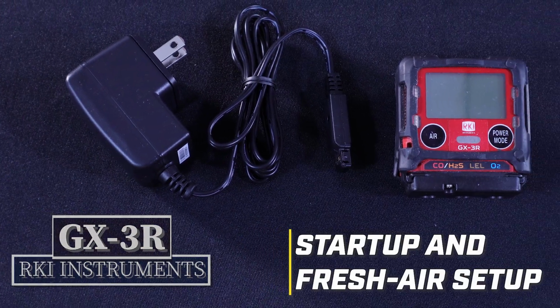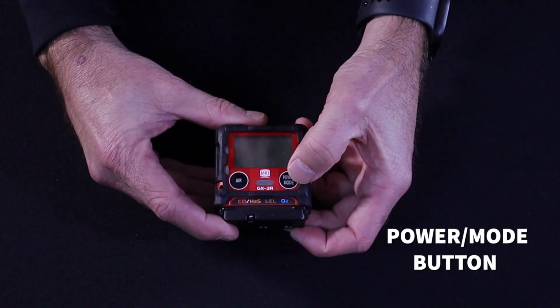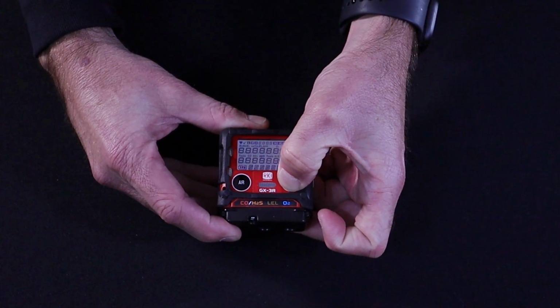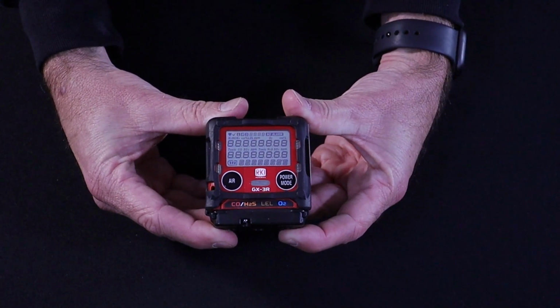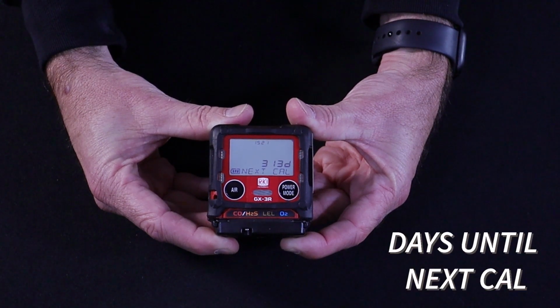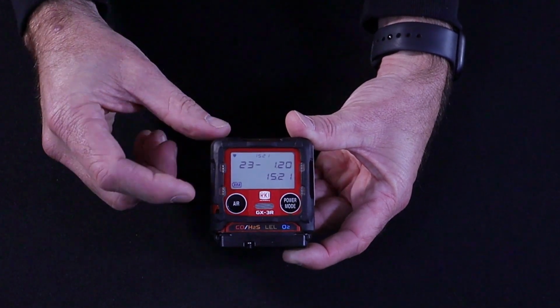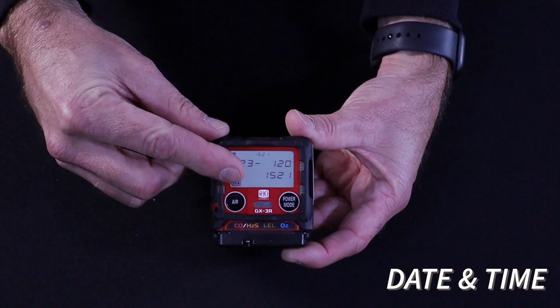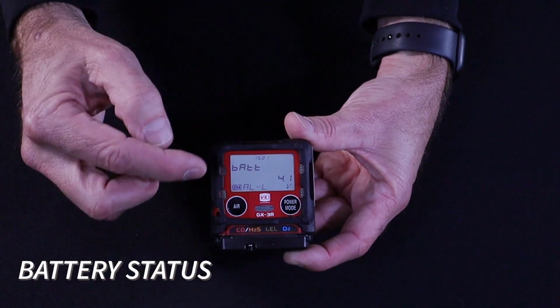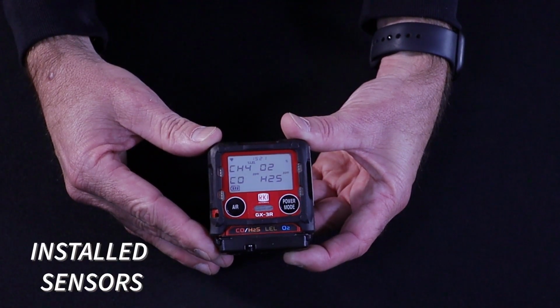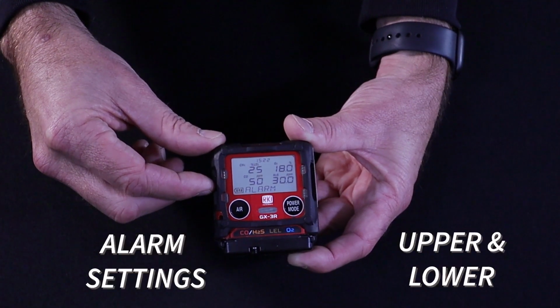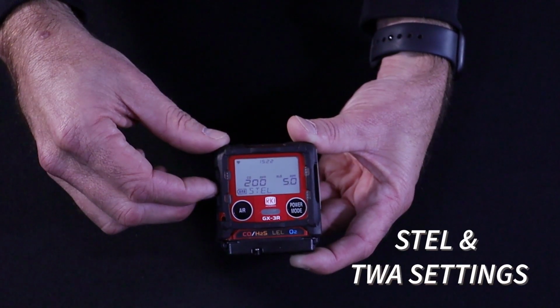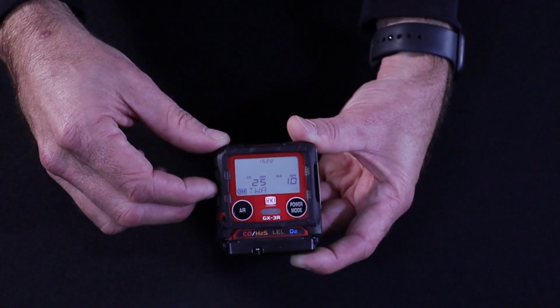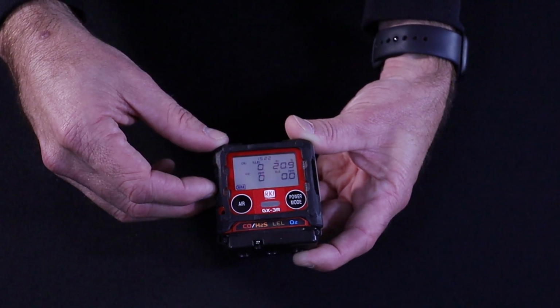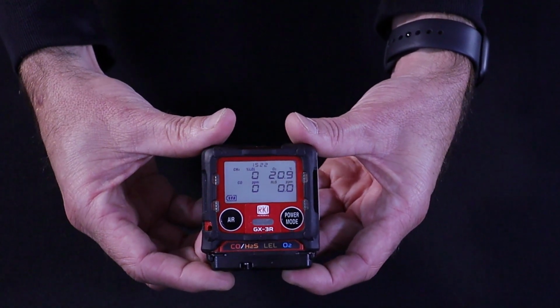Let's go ahead and start the unit up by pressing and holding the power mode button until you hear a beep. During the startup sequence, the monitor will scroll through the set values for days until calibration is required, current date and time, battery status, installed sensors, upper and lower alarm settings, STEL and TWA settings. The unit will then beep twice to indicate that it is in measuring mode.